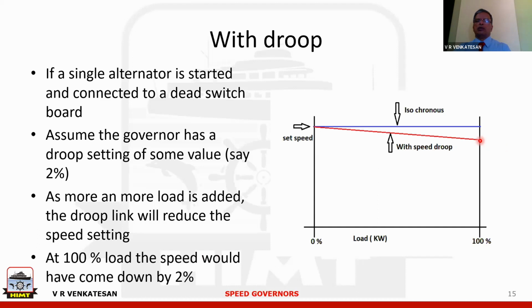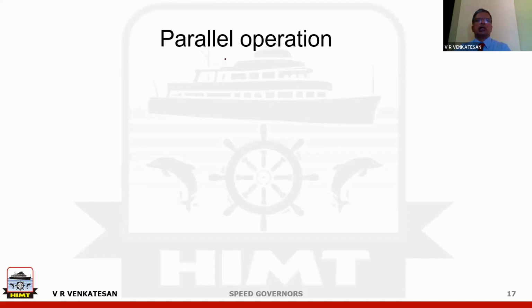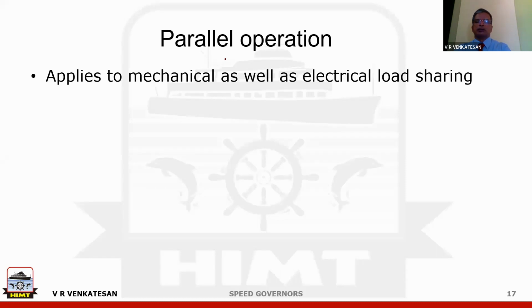So once again, if the engineer wants to restore the speed to 60 hertz, he will move the speed adjusting lever in the switchboard, which will rotate the motor on top of the governor, and the spring force will be increased. And this whole red line will move further up, so that this point will come here. And the red line will be in a position like this now. So let us move on to parallel operation.